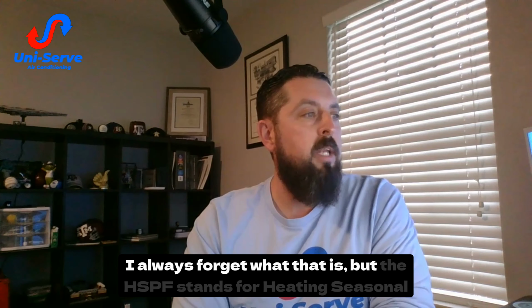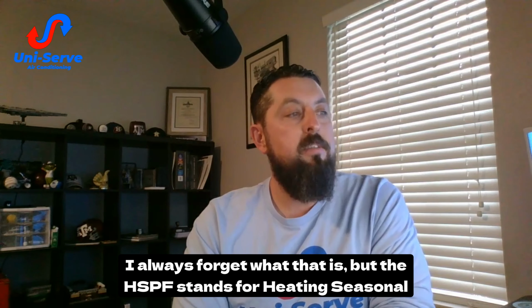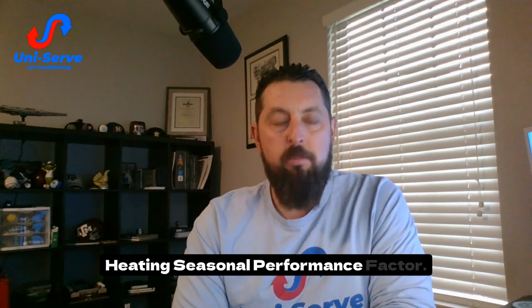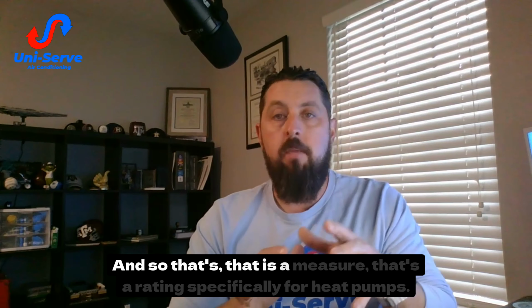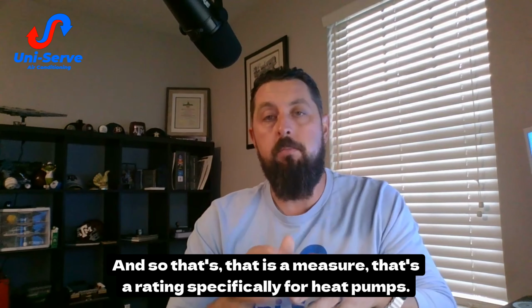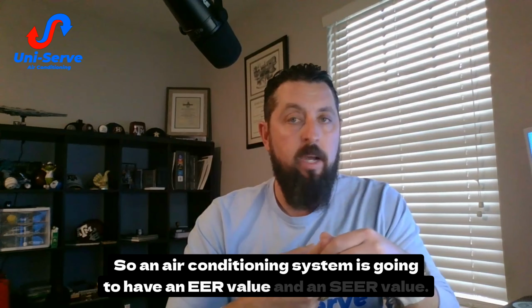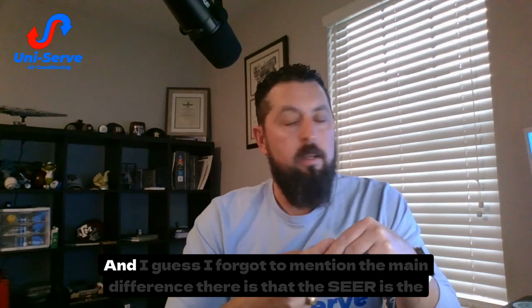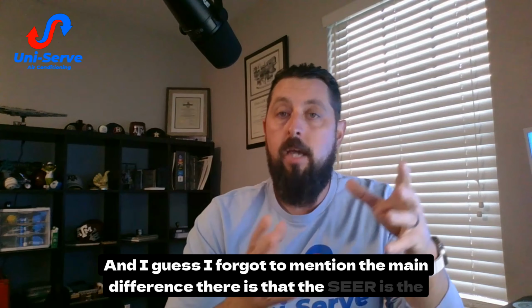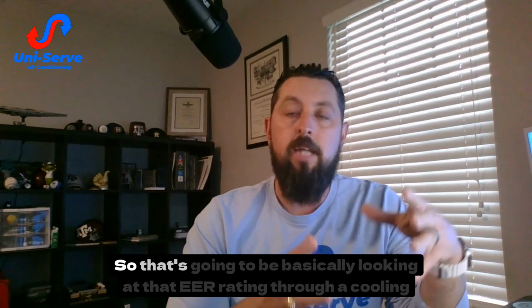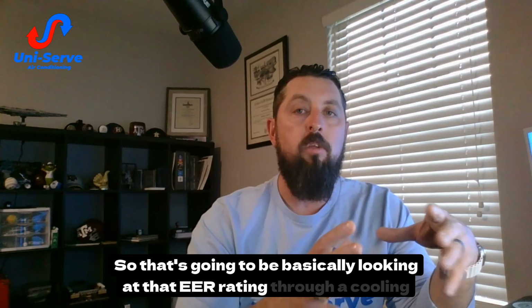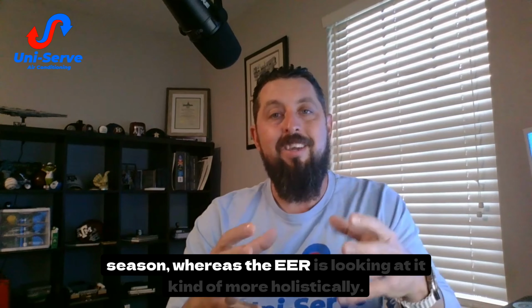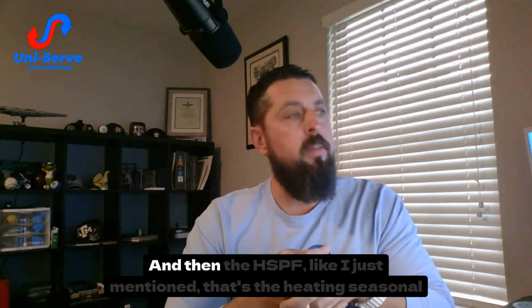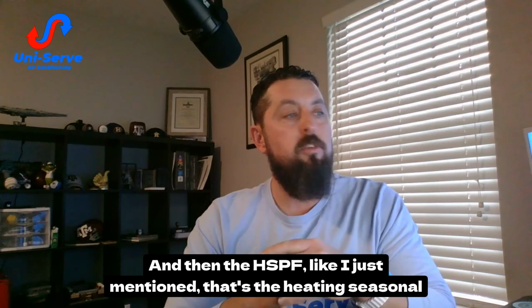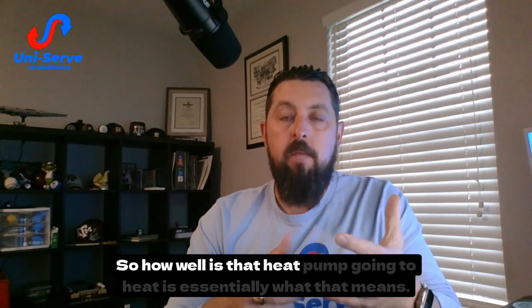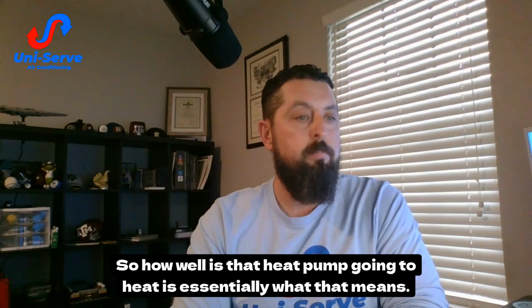HSPF stands for Heating Seasonal Performance Factor, and that's a rating specifically for heat pumps. An air conditioning system will have an EER value and a SEER value. SEER is the Seasonal Energy Efficiency Rating, basically looking at that EER rating through a cooling season, whereas EER looks at it more holistically. The HSPF, as I mentioned, is the Heating Seasonal Performance Factor, so it essentially measures how well that heat pump is going to heat.